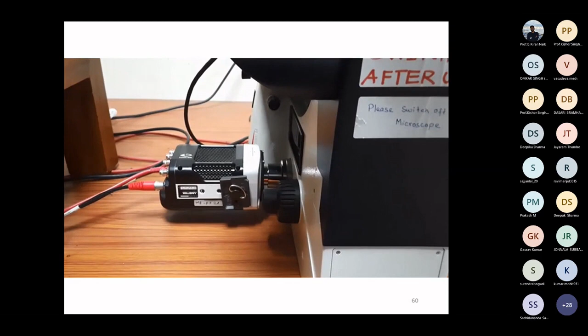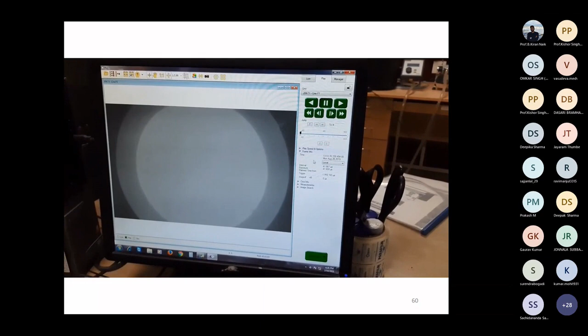For data processing, we use this Phantom camera controller software. We can choose different properties of the frames and camera from here. You can see we can set resolution here. We can also set sample rate, that is frames per second or pixels per second, and exposure time. With this software, we can see info about frames. Here you can see it shows the time when the frame was captured, the interval between two frames, the exposure, and we can also see info about the cine files. Cine files are the files which we capture while recording a flow or recording the process.